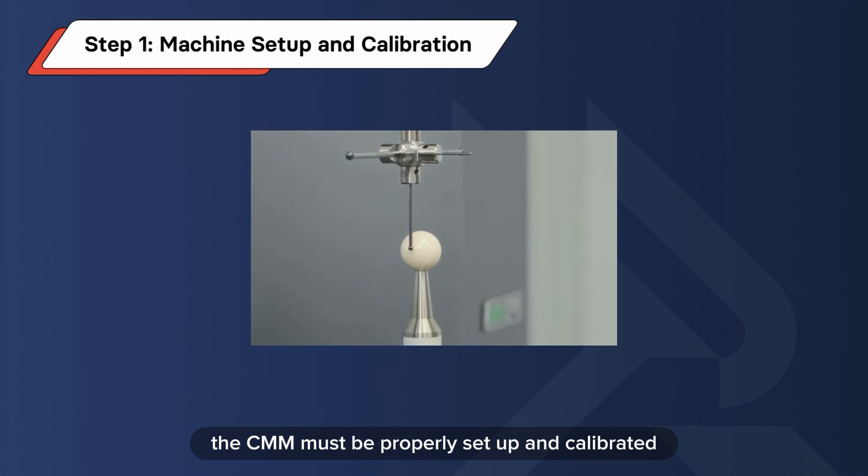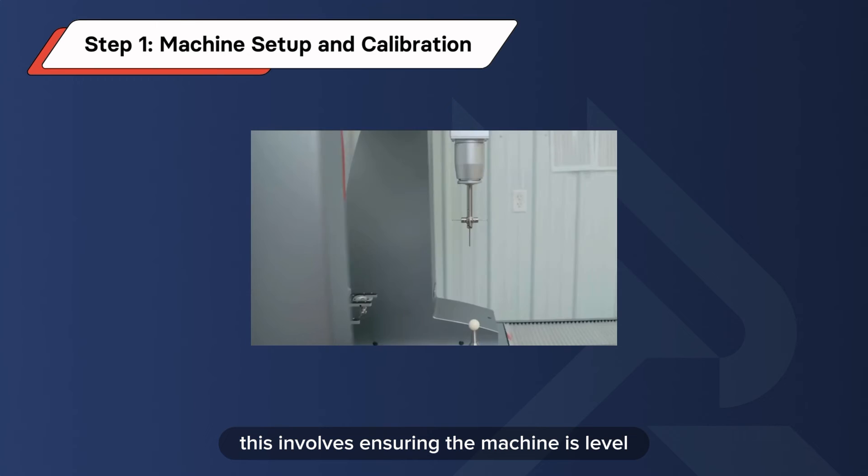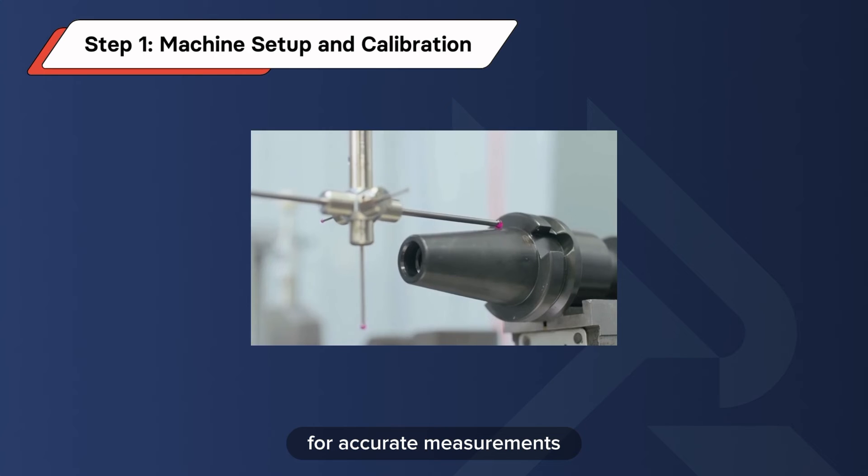Before measurement, the CMM must be properly set up and calibrated. This involves ensuring the machine is level and that its measuring probe is calibrated for accurate measurements.